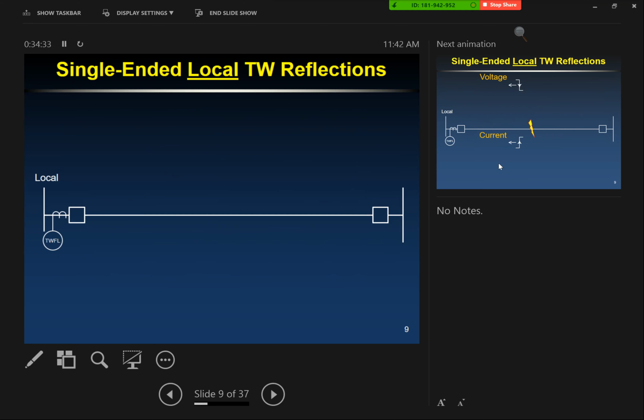And again, this is single-ended. We only have a traveling wave fault locating relay on this end, nothing on this end. And so when I talk about local reflections, we'll put a fault, and I'll be talking about the reflections going in between the fault and the local terminal. I'll go over later the remote end, because you're going to have reflections going in between here and propagating back through too. So let's just focus right now on the local reflections.